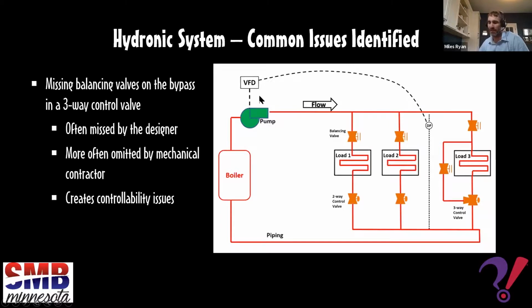were supposed to operate in a lead-lag sequence, meaning that when there were high flow requirements, both pumps are going to be running. On milder days, swing seasons, probably just one pump is going to be running, and it could meet the needs of the system. Well, both pumps were running for like 4 months straight at 60 hertz, full tilt. And before I went into my functional testing, I was scratching my head at why that was the case. Well, they were running at full tilt because they could not meet the differential pressure set point. And I had my suspicions, but when I went out there for functional testing, we confirmed that they had never installed the balancing valve in the bypass leg.